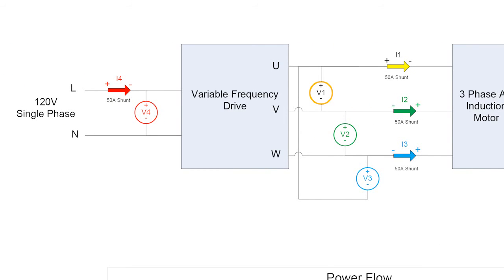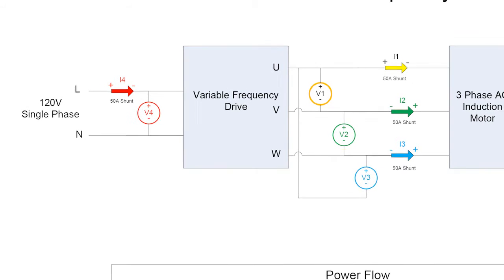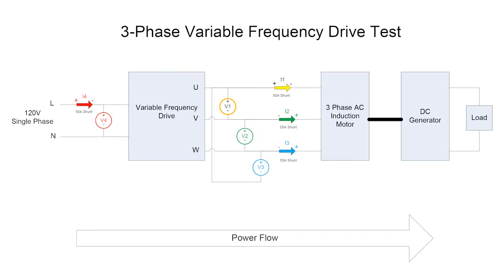I've got my power analyzer wired both on the front end, looking at the 120-volt single phase line in, measuring it with a 50-amp internal shunt and a voltage measurement, and these are all isolated current and voltage measurements. And then on the output, I'm measuring U to V, V to W, W to U as a delta wiring configuration, measuring with each one of the voltage inputs and current inputs one, two, and three. Again, these are 50-amp internal shunts.